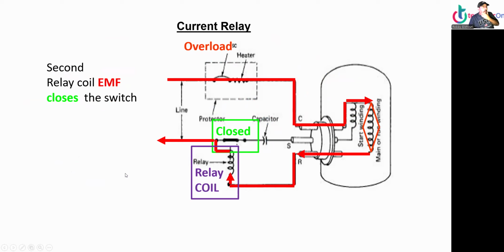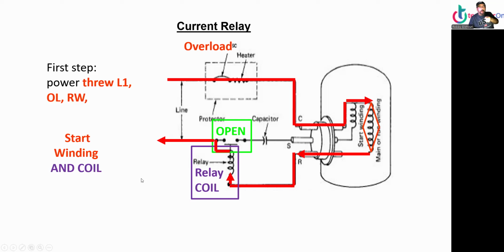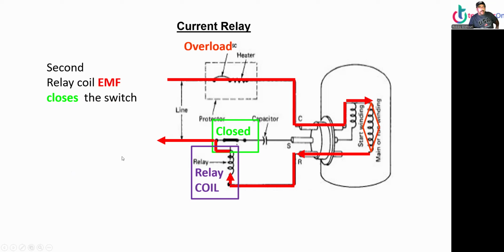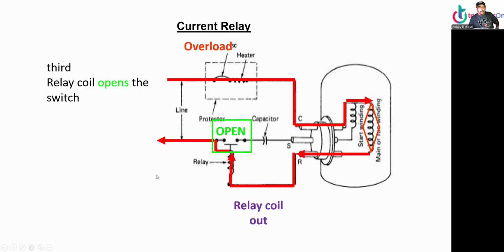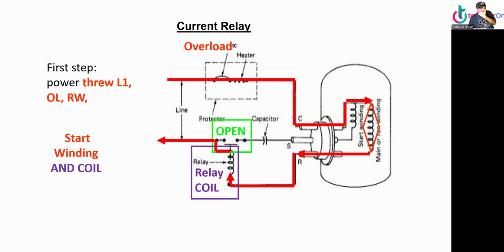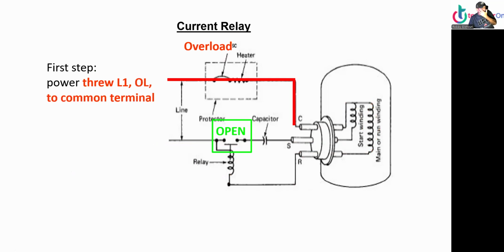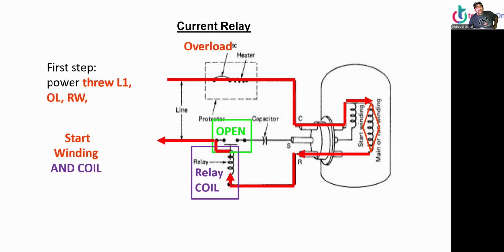Second, now the coil will create a magnetic field and the switch will close. Remember, switch open and power goes through the relay coil. Now the switch closes and power goes through the start winding. Now the relay will open and continue to run only through the run winding. So first, switch is open, it goes to the run winding first, creates a super high amperage.